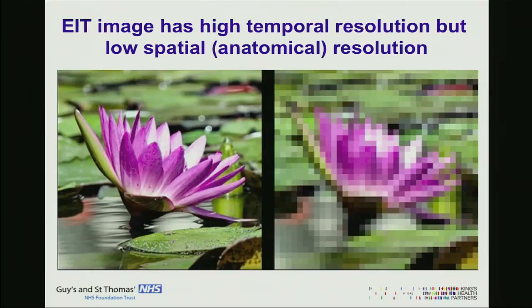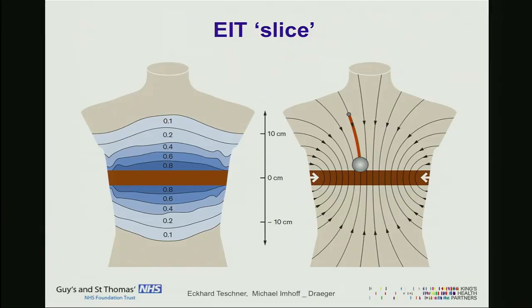The slice that EIT provides is not the slice we are used to with CT scan. X-rays travel in a linear fashion, whereas electricity doesn't — it is non-linear. Therefore, we have a large band or thick slice with EIT, which depends on the size of the patient, but it is between 7 and 10 centimeters across the band. That is what the image is — a thick slice that EIT can image.